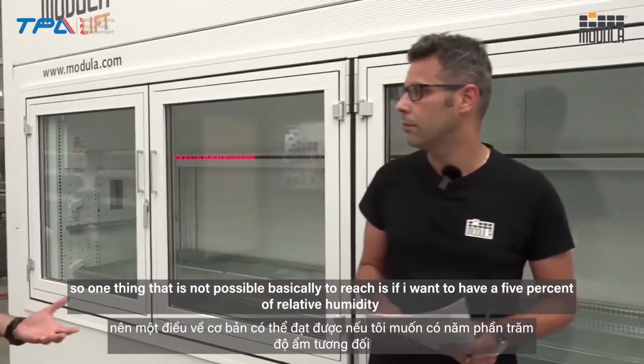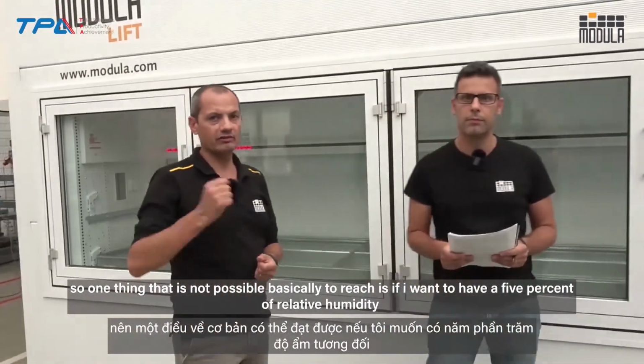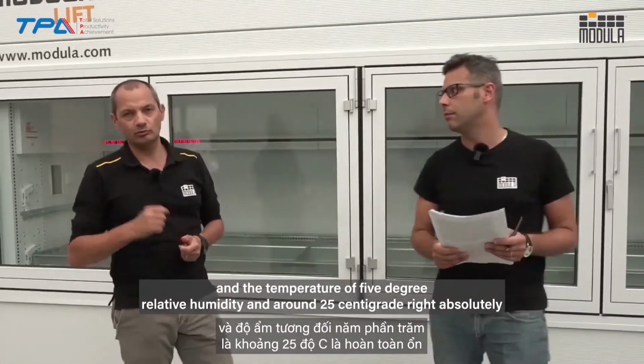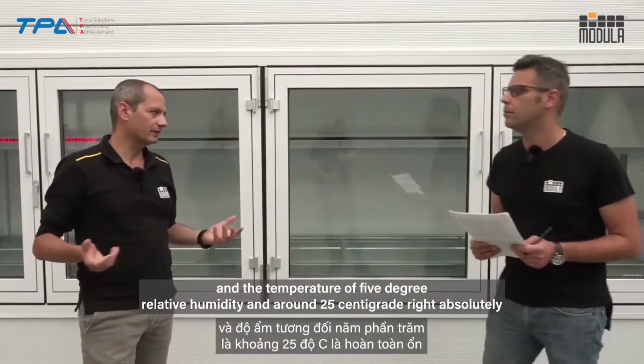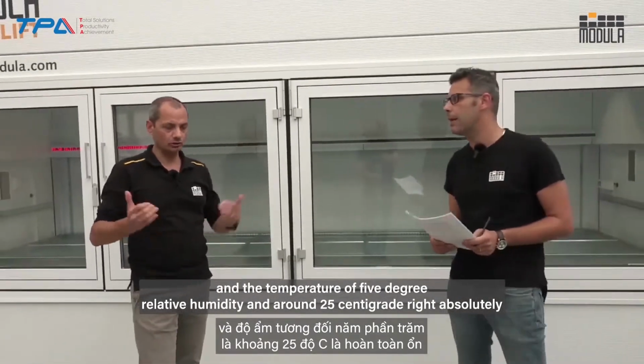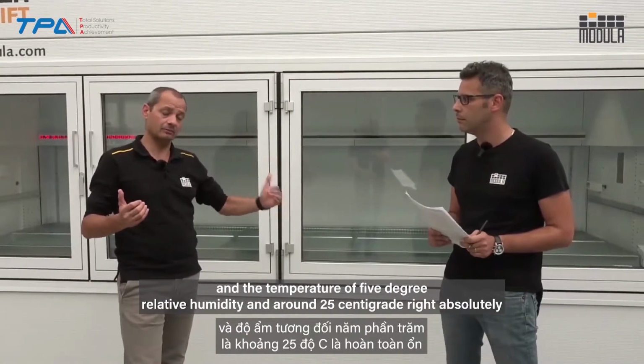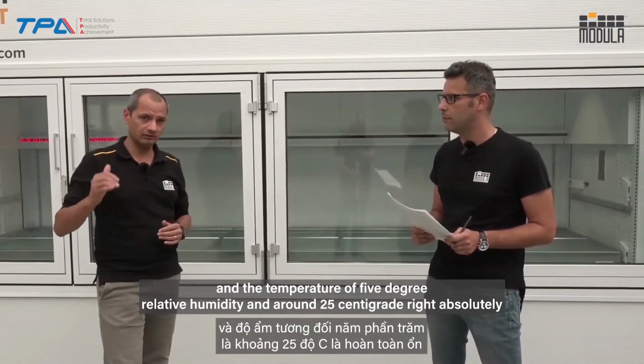So one thing that is basically not possible to reach is, if I want to have 5% relative humidity at a temperature of, I don't know, 5 degrees centigrade, that is something that we cannot reach. So the two limits are 5% relative humidity and around 25 centigrade, right? Absolutely. Okay.